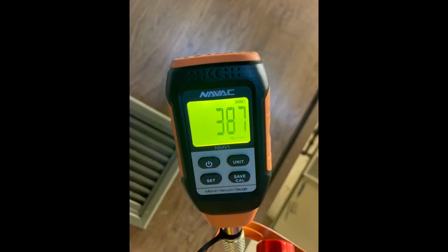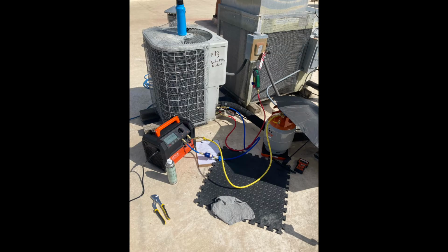So ideally, you want to pull down below 500 microns or as low as your vacuum pump will pull a vacuum on that tank. Now up on the roof, we have our recovery machine, recovery bottles set up, the power's turned off, the compressor's dead anyway. We have our manifold gauge set up. We're going to go ahead and recover all the refrigerant out of this old split system.